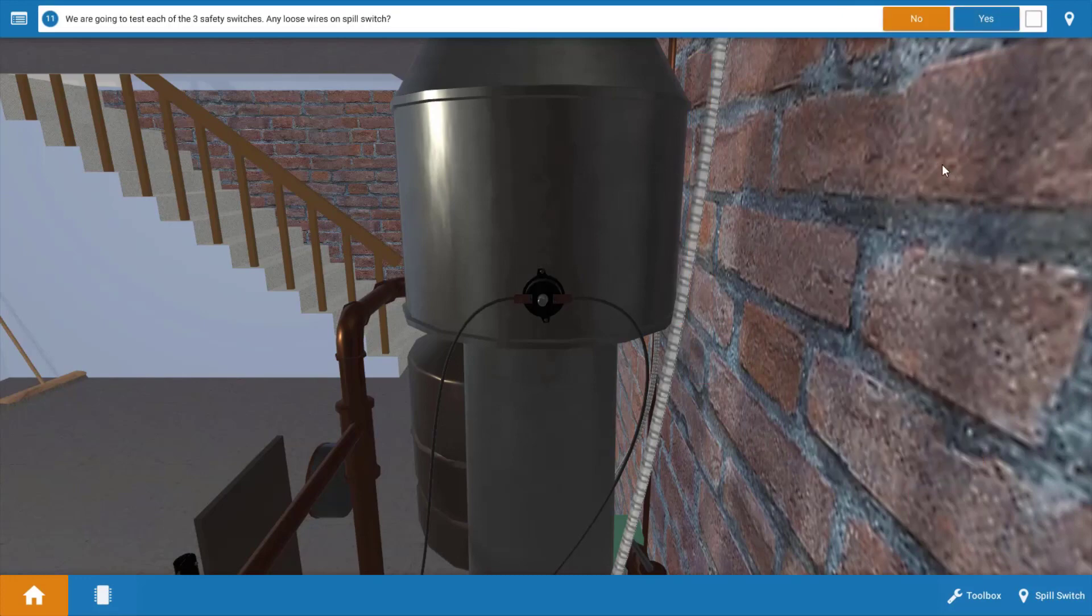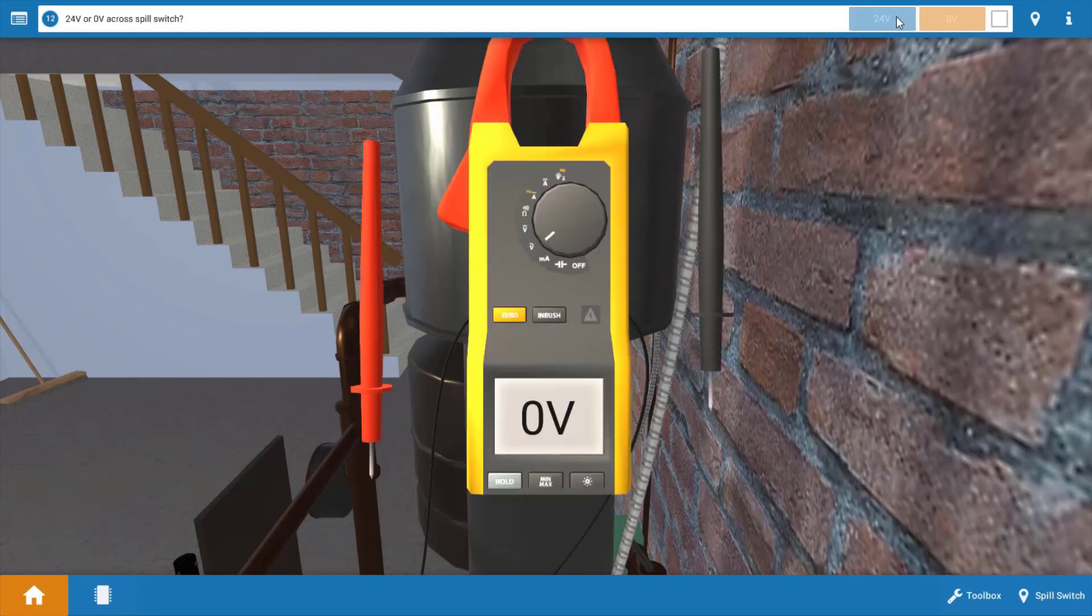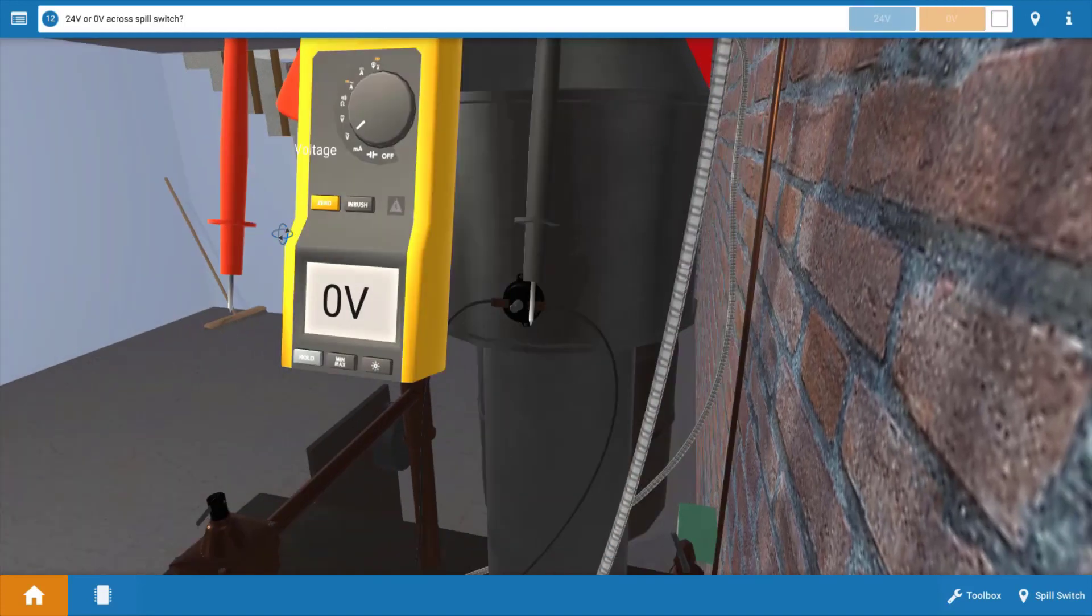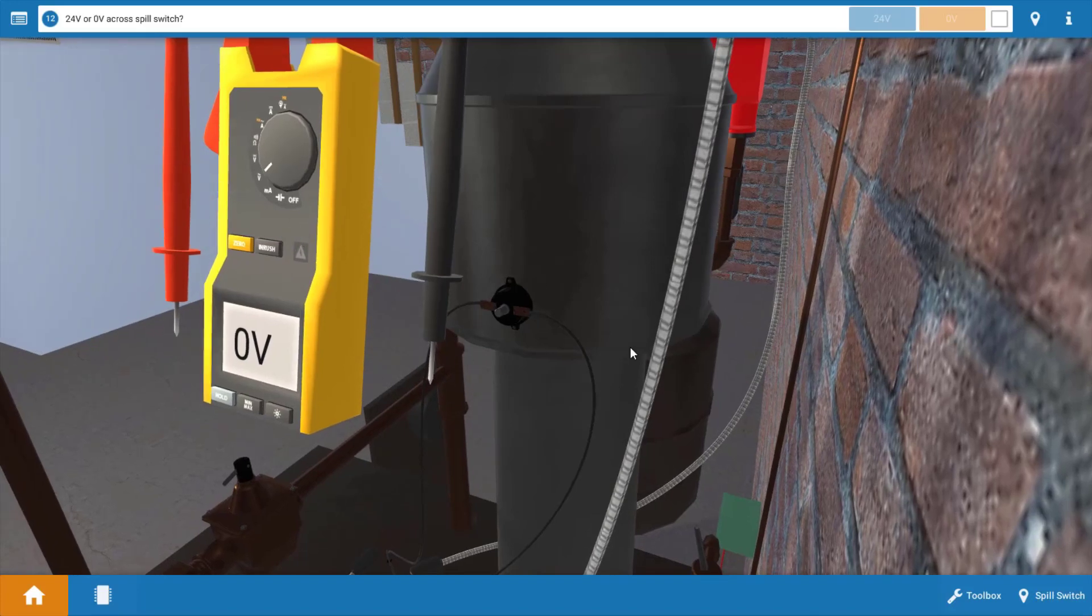Next, we're going to check the spill switch. Now if you look at the spill switch, there doesn't appear to be any loose connections on the two wires. They appear to be secured, and this is the spill switch right in the center here. Now we're going to measure for voltage across the spill switch, just like we previously have done with the vent damper end switch. We're going to place the lead across each connection point.